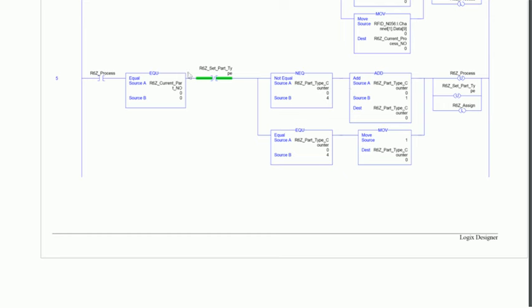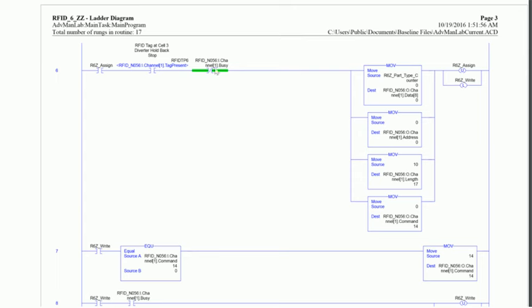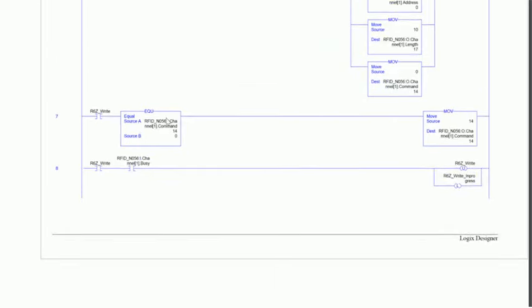With the help of a tag called 'SetPartType,' after this process I do a very similar preset step — moving certain values to address, length, command, and the data field. The key difference here is that instead of data0, I'm using data8, which is where I want to put the number to write, rather than to read. Then I check the input again to verify command was set to zero, and if correct, I set command to 14, which means 'write' — remember, 4 is read and 14 is write. There are at least 20 different command codes, all the way up to 32, and you can look them up in the RFID manual provided for our testbed.